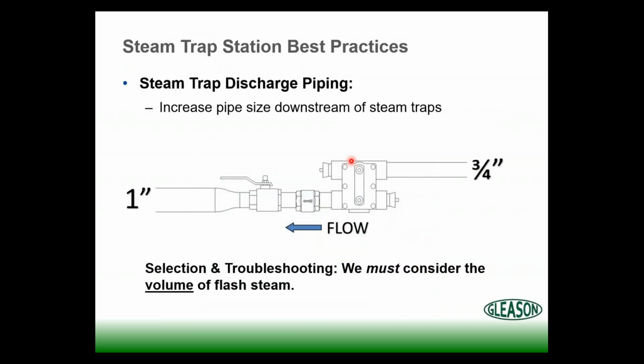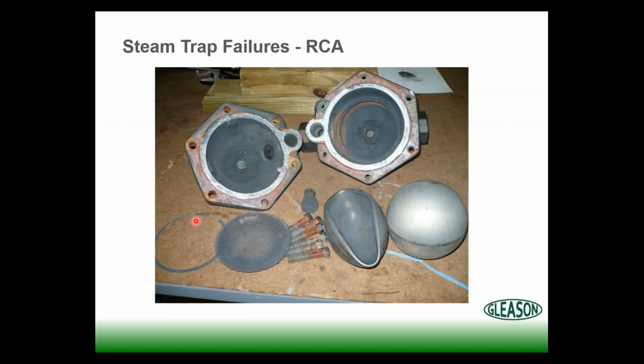Another best practice: downstream of a steam trap, we're going to go up a pipe size. So if we're coming in 3/4, we go out 1. Or I'm sorry, if we go in a 1/2 inch, we're going to come out a 3/4 inch. The reason we do that is we have to give the volume of the flash steam somewhere to go. We won't get into flash steam in this session, but there's a lot to be considered there. Best practice calls for going up a pipe size. We've got to give the volume of the flash steam somewhere to go.